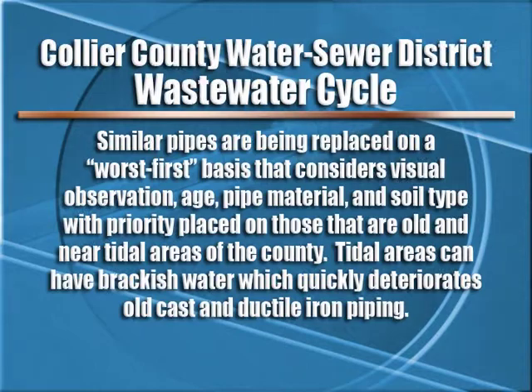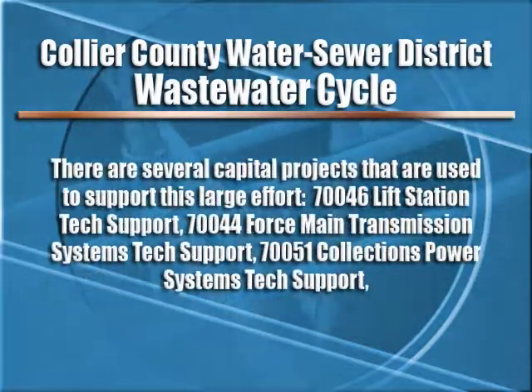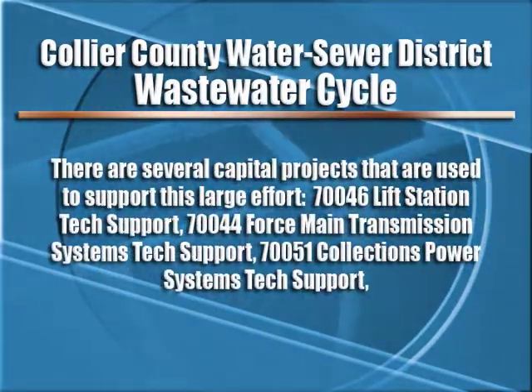Similar pipes are being replaced on a worst first basis that considers visual observation, age, pipe material, and soil type, with priority placed on those that are old and near tidal areas of the county. Tidal areas can have brackish water, which quickly deteriorates old cast and ductile iron piping. There are several capital projects that are used to support this large effort.